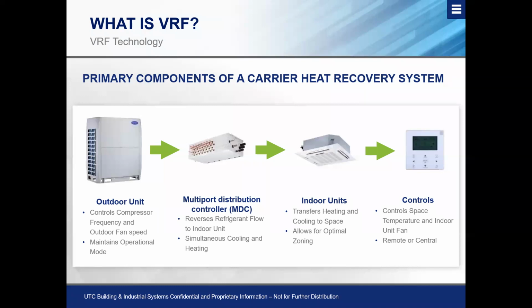We have an outdoor unit. We have our multi-port distribution controller, which we know now has a gas liquid separator to create those three states of refrigerant. It has a brazed plate heat exchanger to help subcool that liquid refrigerant so we can get greater piping distances. And it has solenoid valves that essentially act like stoplights in a traffic intersection to control refrigerant flow depending on what indoor unit or units need it. And then, of course, we still have some form of indoor unit that's connected by refrigeration piping, and then some form of control, whether it be wired, wireless, or centralized.